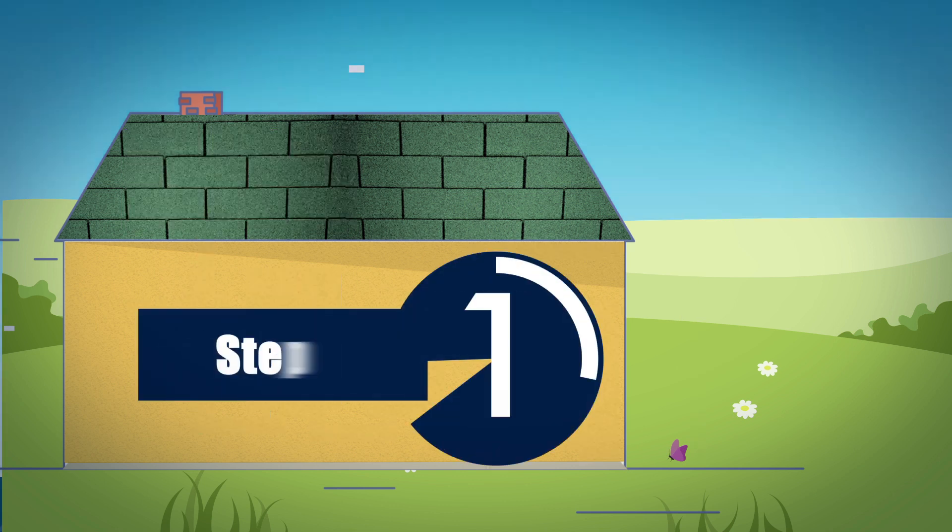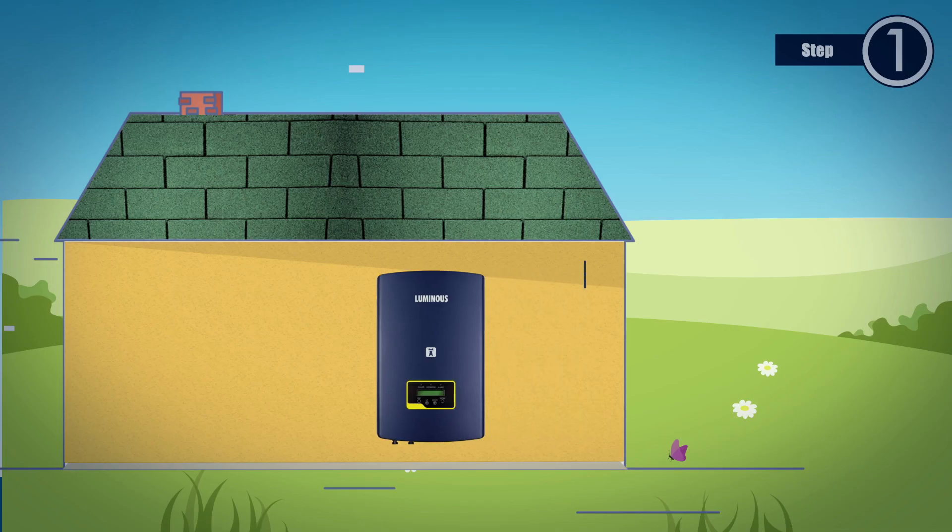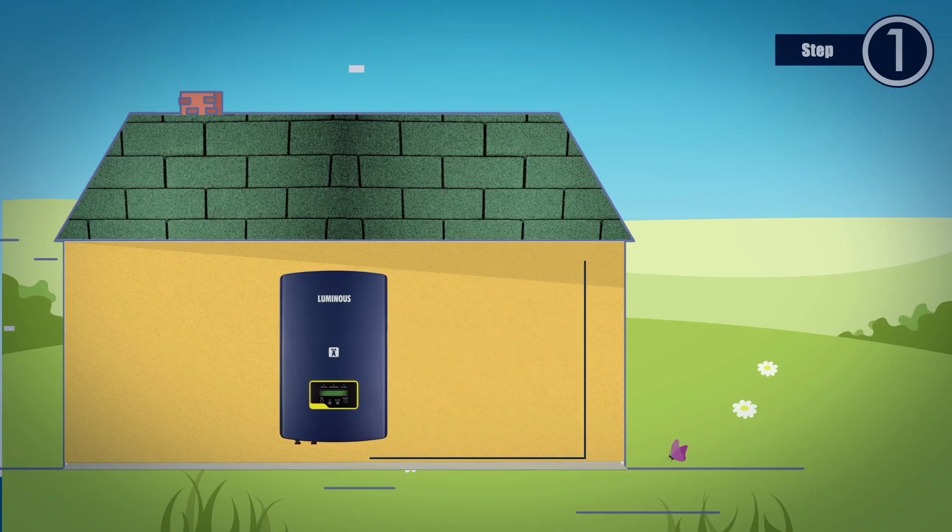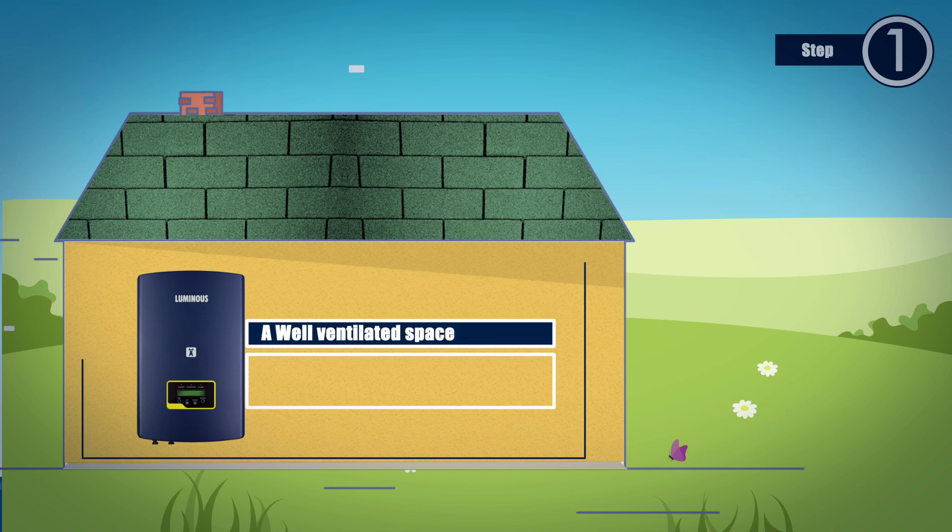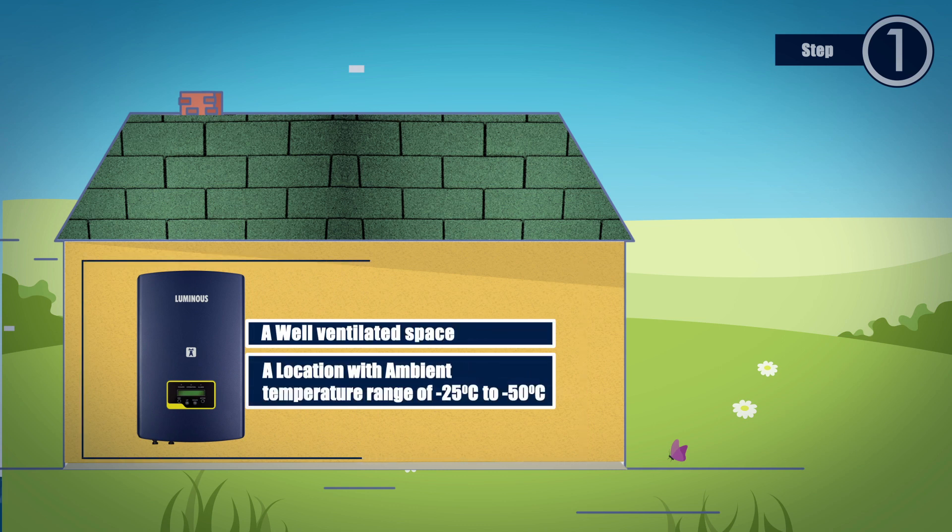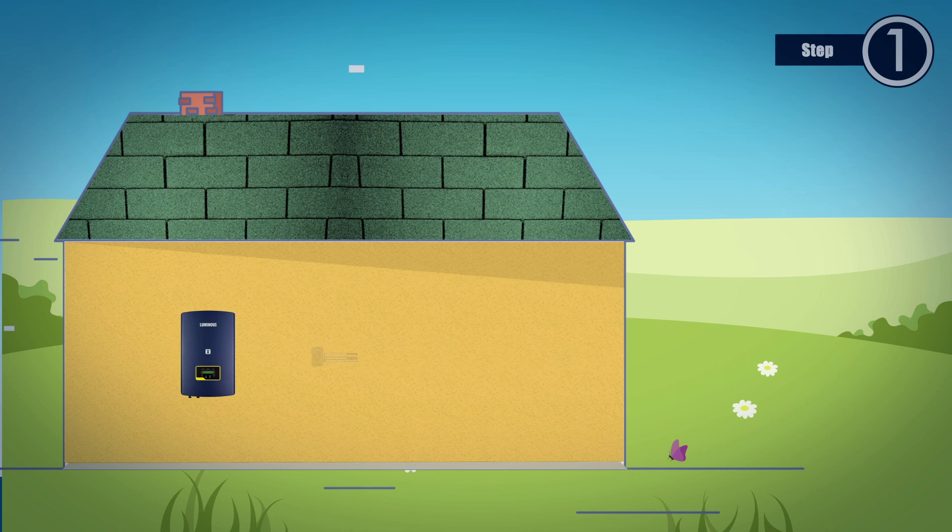Step 1. Select the right location for the inverter installation. The inverter should be installed in a well-ventilated area where the ambient temperature is in the range of minus 25 degrees centigrade to 50 degrees centigrade.